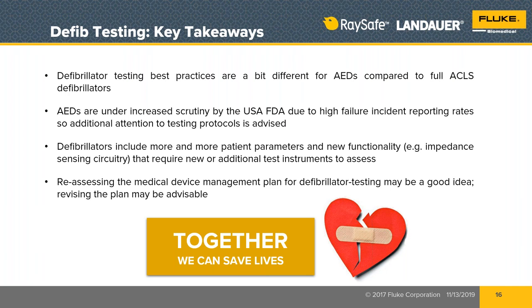Be sure your test instruments are keeping current with the innovations and changes in the medical device. We talked about output energy guarantee. We talked about pulse co-oximetry built into the defibrillator. We talked about pacemaker testing that are built into the defibrillator. So keep looking at your test instruments compared to the functionality in these medical devices. Be sure you understand them. Go to the service school that the manufacturer provides for these if you can, because you will learn so much and it will make it so much easier for you to identify problems early while they're less expensive and easy to fix.